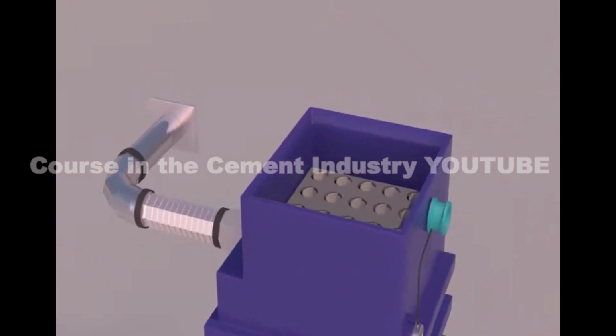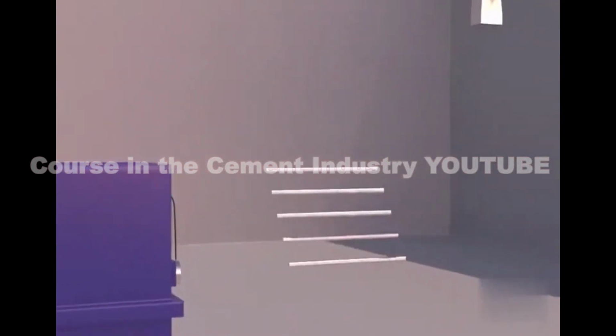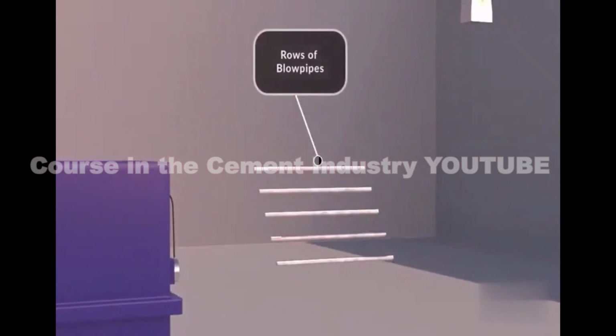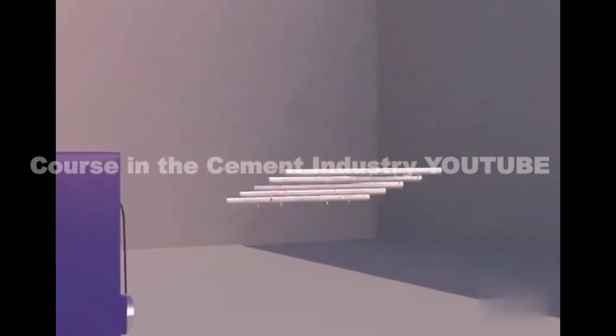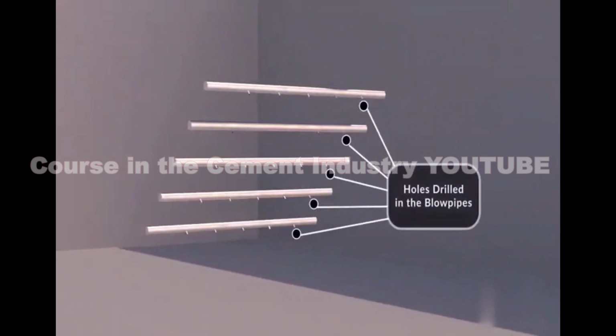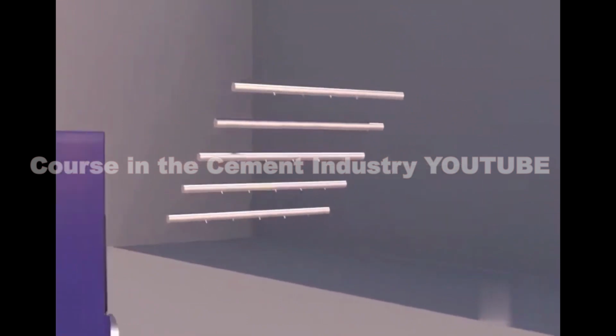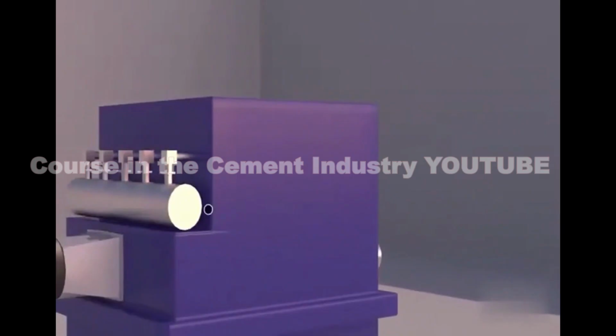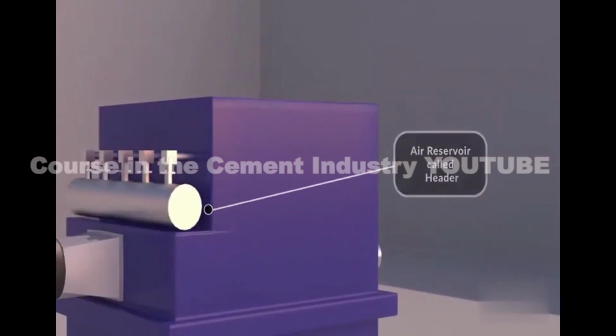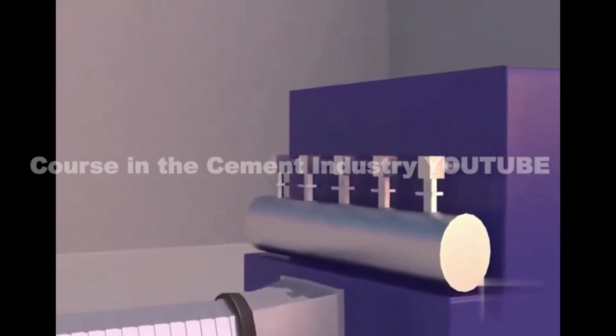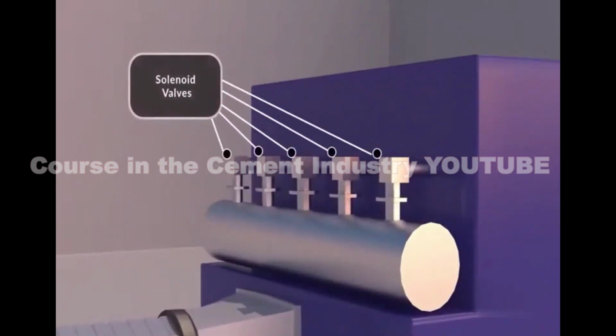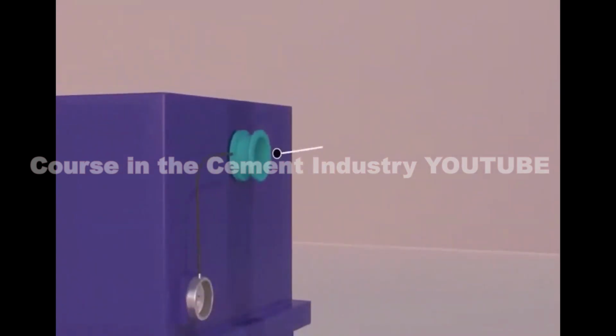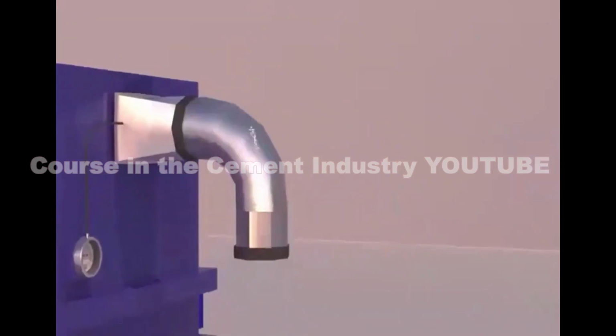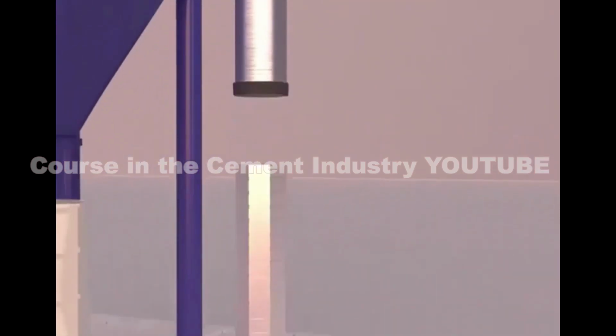Above the tube sheet, in the upper body, is the cleaning system of the machine. This includes a series of blowpipes. Each blowpipe is drilled with holes and is connected to an air reservoir called the header, which has solenoid valves attached to it. The upper part also includes an outlet, which is connected to a series of pipes used to carry the filtered air.